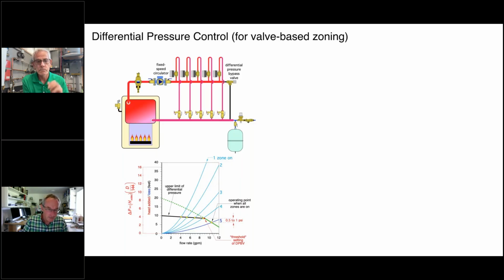In this case, we'd have a flow rate of about 10.5 GPM and a relatively low differential pressure across the circulator. Well, as we start to close down the zones, 4 zones open, 3 zones open, 2, and finally only 1 zone, you see how these system head loss curves are getting steeper. That implies you're getting higher and higher differential pressure across the circulator, and it also means the active zones are seeing higher and higher flow velocity.